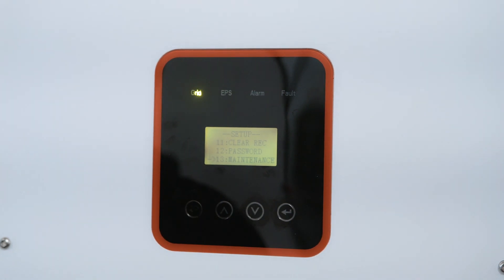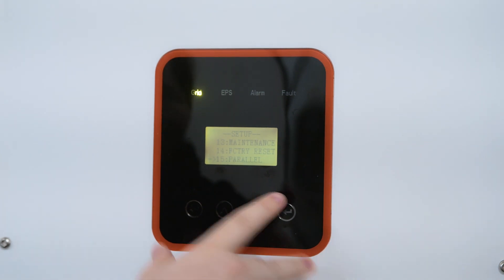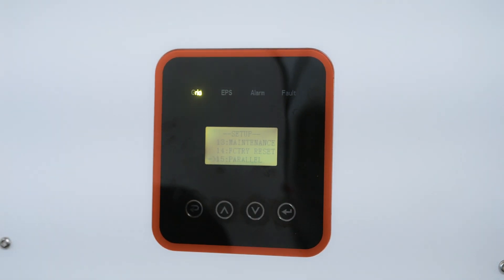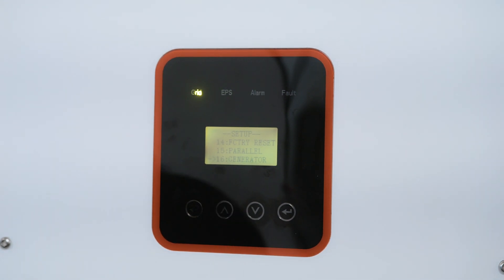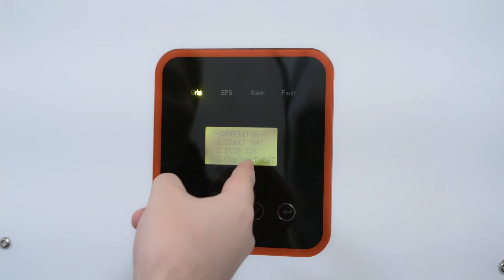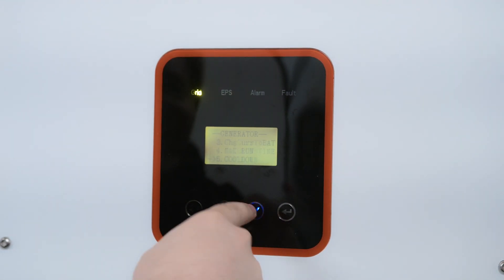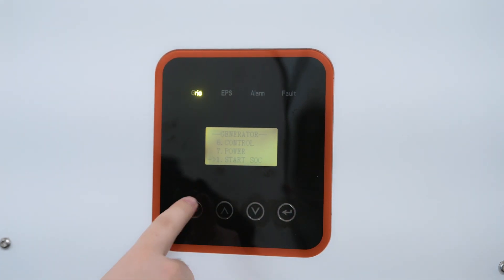Maintenance is a bunch of internal settings, so we're not going to mess with those. Factory Reset we don't want to do unless there's a big problem. Setting 15 is Parallel — if you're going to be setting up multiple inverters in parallel, you want to go in there and set them up. And then finally, with the new firmware update, we have the Generator setting. We can go in here and configure start SOC, stop SOC, charge current to batteries, max runtime, cool down control, and power — there are a lot of settings with the new generator firmware update.